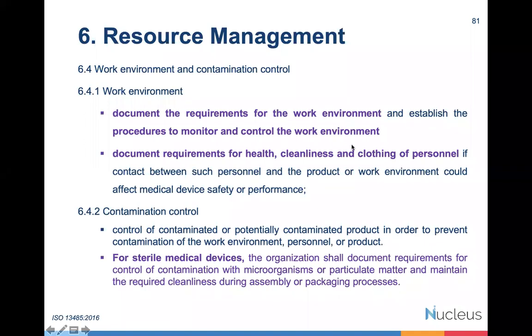Typically, most of the medical devices used in critical care are sterile products, it depends on what role you are playing. So we can simply say, hey, the 6.4.2 requirement for sterile medical device is not applicable. The non-applicability can be claimed here, but we cannot exclude this.